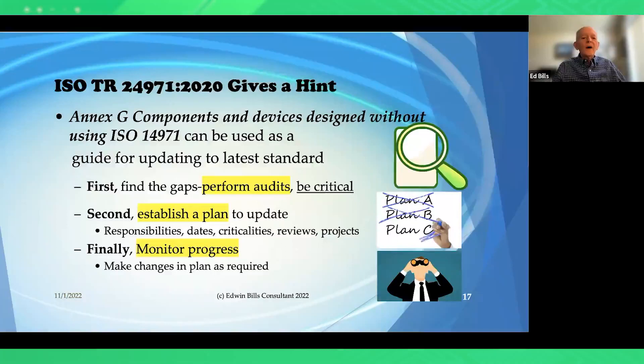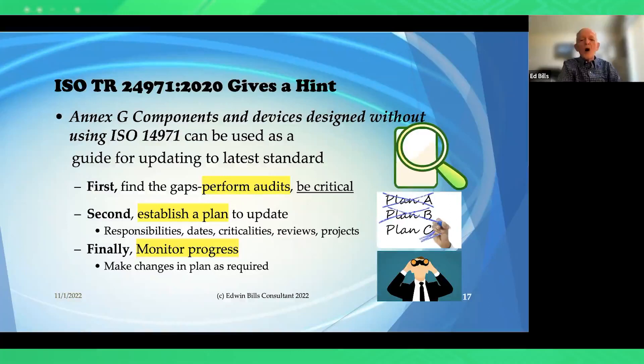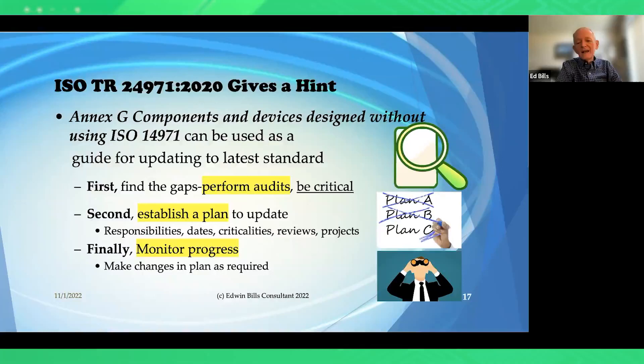How can organizations get on track? Annex G of ISO TR 24971-2020 provides guidance on components and devices designed without using the latest edition of ISO 14971. First, find the gaps — perform audits, be critical, find all problems. Second, establish a planned update identifying who is responsible, the dates, criticalities, reviews, and projects needed. Finally, monitor progress and make changes to the plan as required — because the plan at the start rarely looks the same at the end.